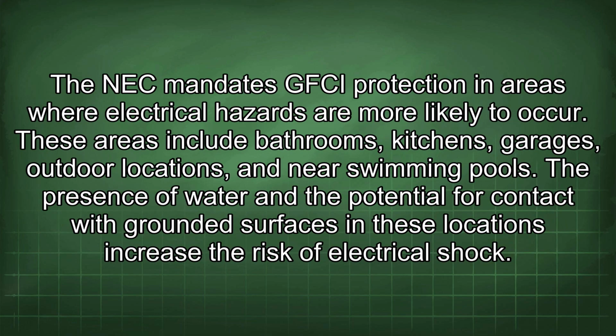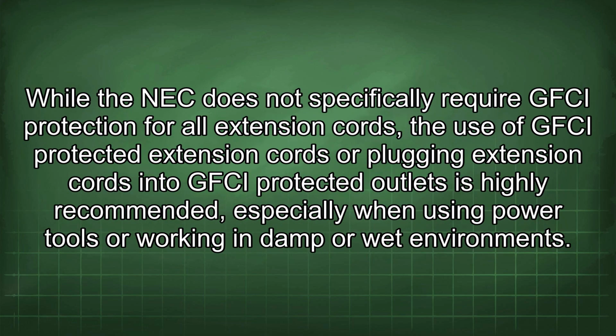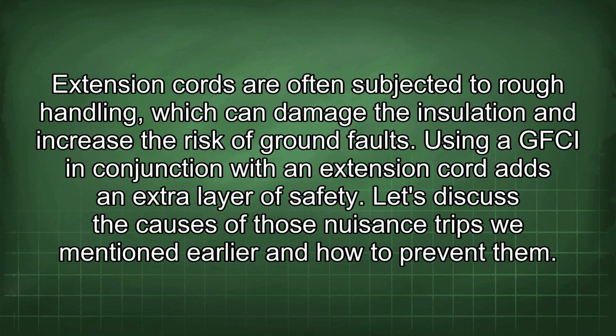The NEC mandates GFCI protection in areas where electrical hazards are more likely to occur. These areas include bathrooms, kitchens, garages, outdoor locations, and near swimming pools. The presence of water and the potential for contact with grounded surfaces in these locations increase the risk of electrical shock. While the NEC does not specifically require GFCI protection for all extension cords, the use of GFCI protected extension cords or plugging extension cords into GFCI protected outlets is highly recommended, especially when using power tools or working in damp or wet environments. Extension cords are often subjected to rough handling, which can damage the insulation and increase the risk of ground faults. Using a GFCI in conjunction with an extension cord adds an extra layer of safety.